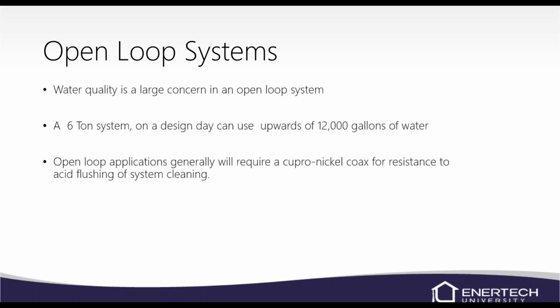Obviously, water quality is a large concern in an open loop and a closed loop system. You know, that's another reason we don't want to just run water through the system all the time. You could use up to about 12,000 gallons of water in a day if that pump just runs and runs and runs. So make sure you're always putting in the proper valves and things, and you're checking your water quality.